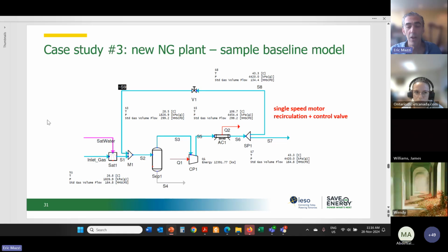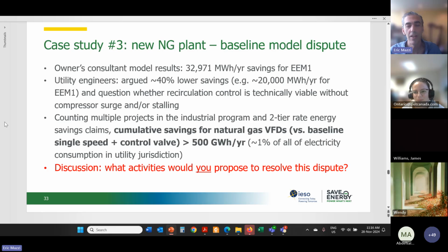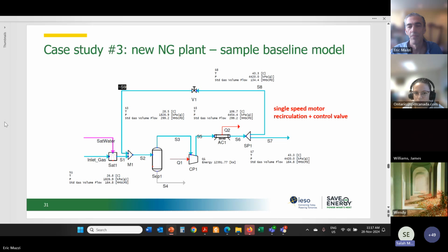Yeah, I agree with all of that. And having said that, we still had some disputes here, but I agree 100% with what was just said. Absolutely. Salah, did you have more comment, or was that your hand? Just quickly, if you sub-meter that motor, which has the VFD on it, and then you basically disable the VFD for a short period of time and mimic that in the model and see if you get the results. That's excellent. Yes, that has happened.